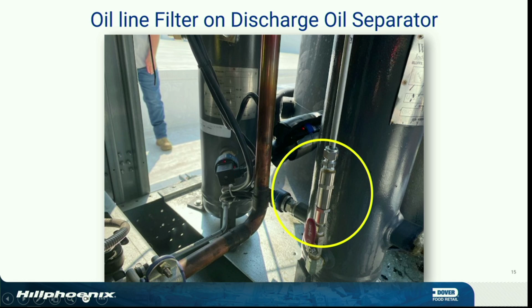This you saw earlier in one of Rusty's pictures. It's about the size of your pinky, that little porous rock that's in there. It does clog up fast, so it's important to keep your oil system clean and your separator filters changed. I would carry an extra one or two on your truck. If you come across one that's clogged up and you're not getting oil transfer, I would pull that one out, put the new one in, then you can take the old one apart, clean it, and put it back in service for later on the same rack.